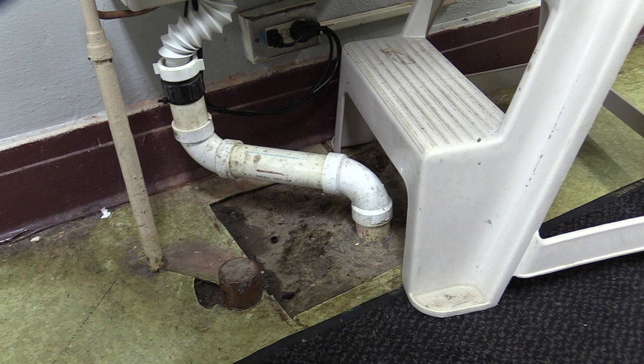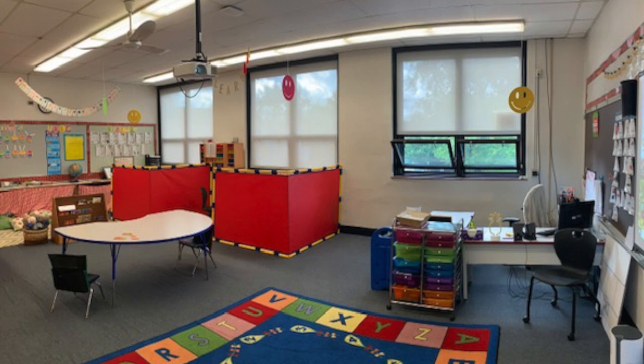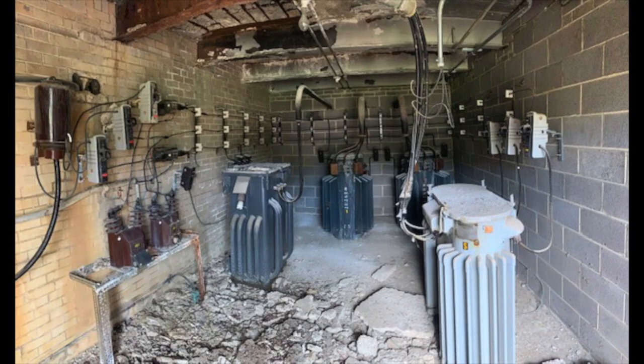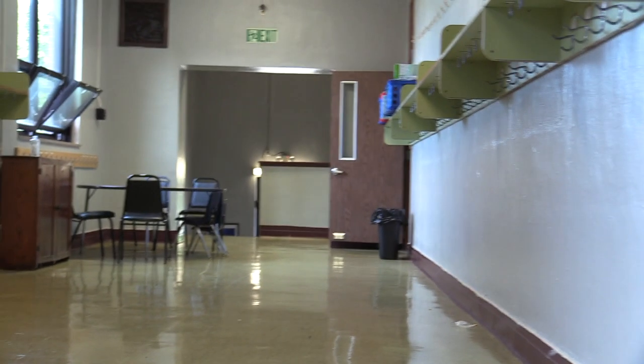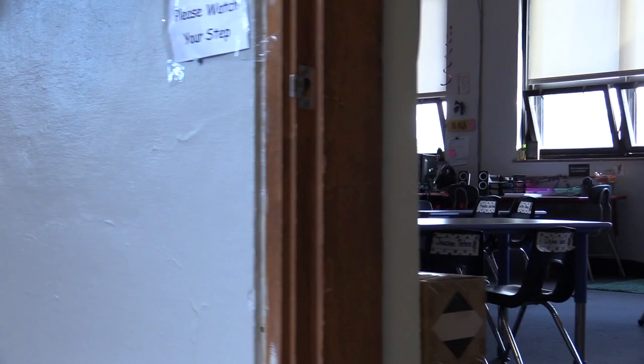This had been semi-repaired here, but there's a perennial leak. These rooms are awfully hot, especially on the south side. Staff say they'll just buy their own air conditioner, but I'd have to run electric — some of these rooms don't have enough electrical capacity for it. From there to where that light is down there is the 1934 addition, just connecting the gym to the 1912.